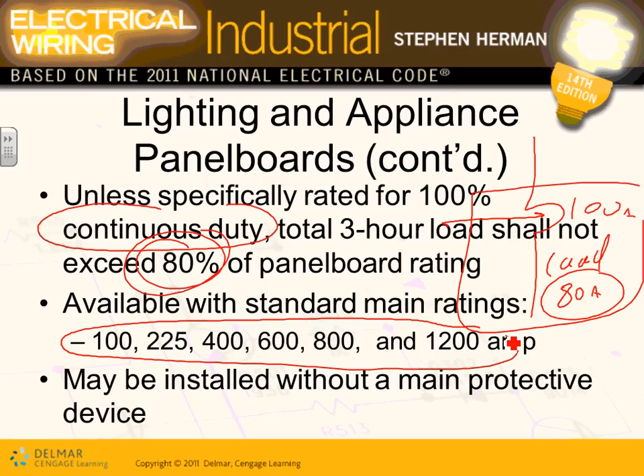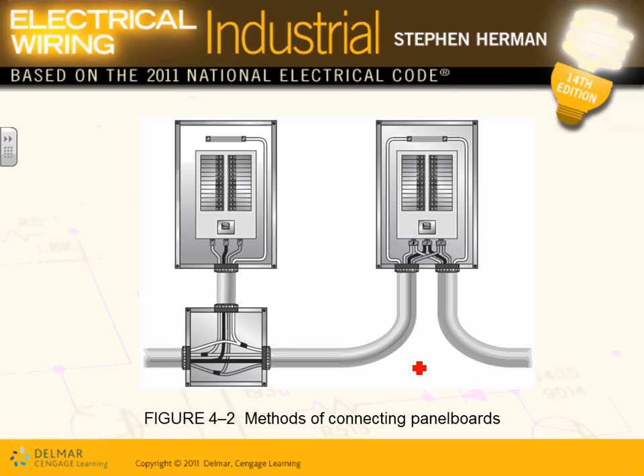You can install them without a main, as long as you have the overcurrent protection device outside. So you have to have a circuit. Look at this one. This is a main lugs only, Adam. And this, where's the main for this circuit breaker? Somewhere else, right? Main lugs only. So that's your panel. You can tap the panel, guys.